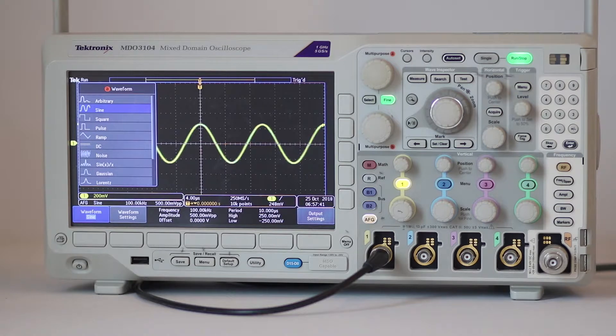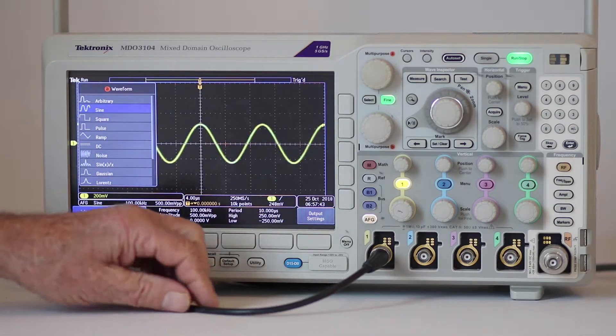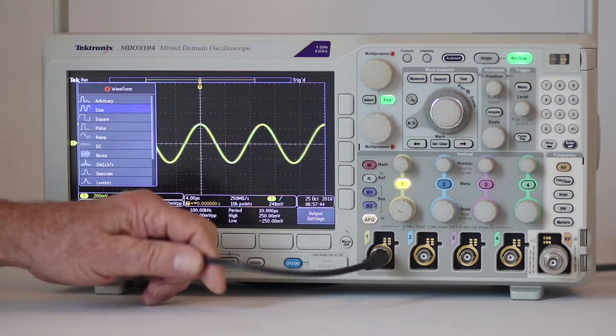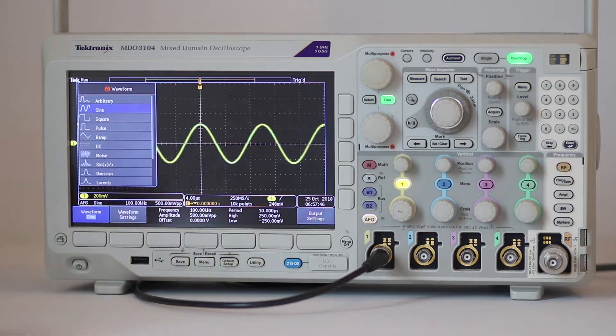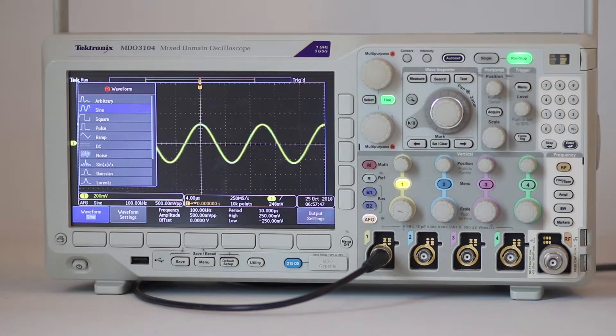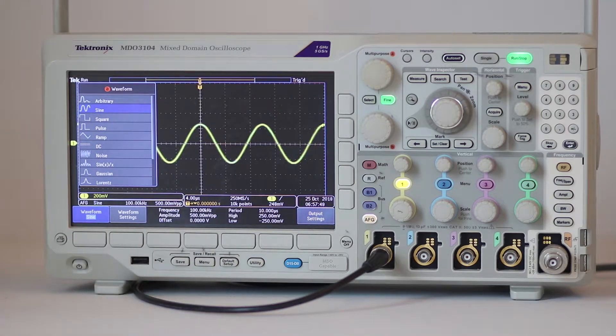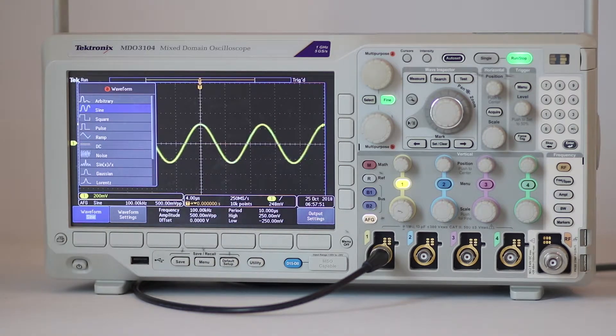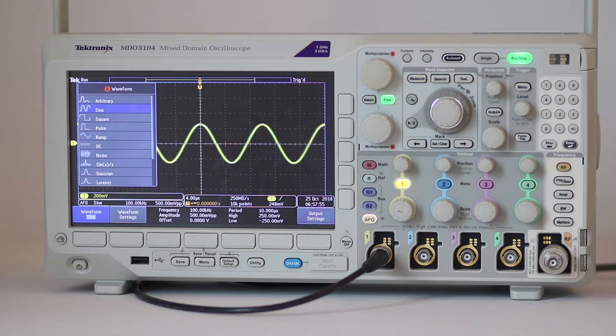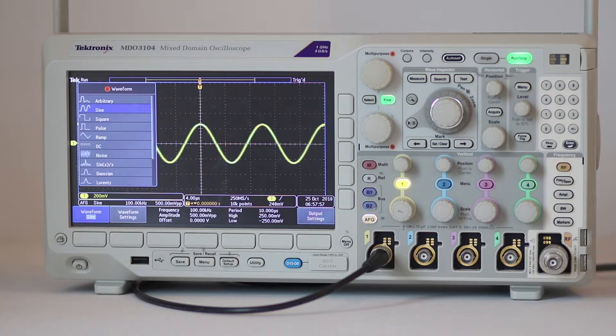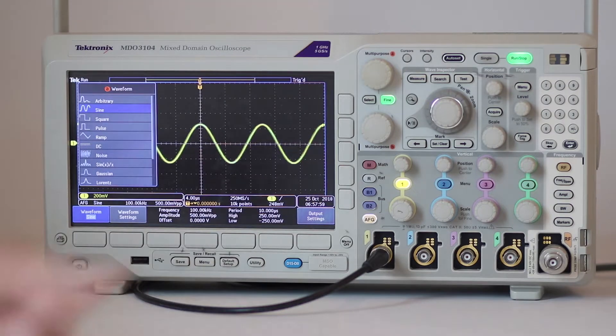To access it we simply connect AFG out on the back panel to one of the analog channel inputs on the front panel using a BNC cable. Then we press AFG on the front panel and the default sine wave appears.